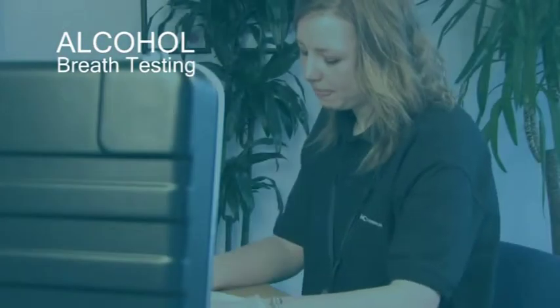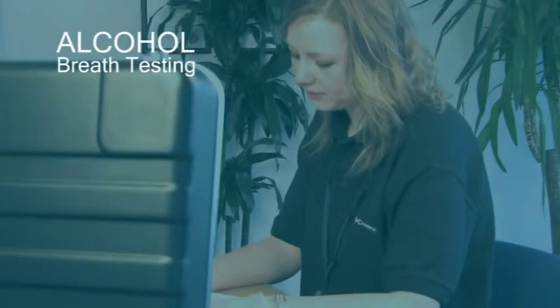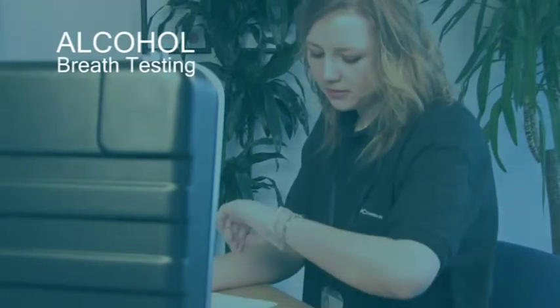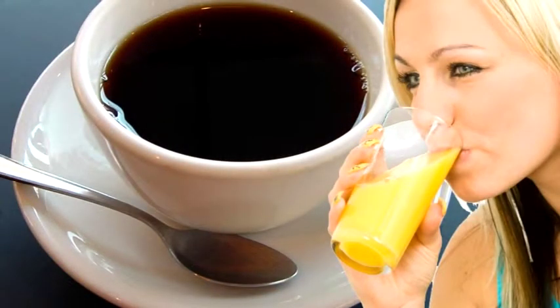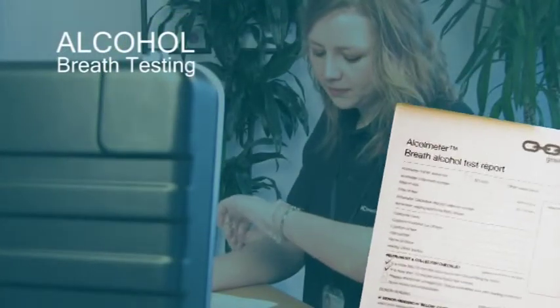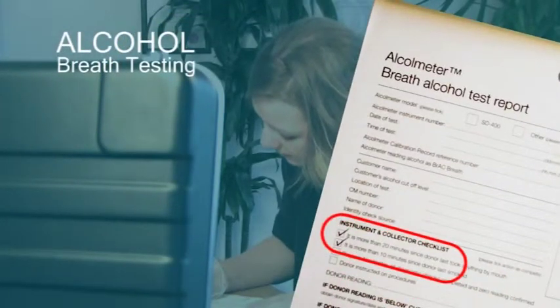This is why we check that the donor has not taken anything by mouth in the 20 minutes prior to the test. We say anything because very hot or very cold drinks could affect the temperature of the mouth and consequently the breath that passes through it, and this arguably could have an effect on the alcohol level obtained. Being rigorous on this 20-minute rule means we can be certain that the results are accurate.